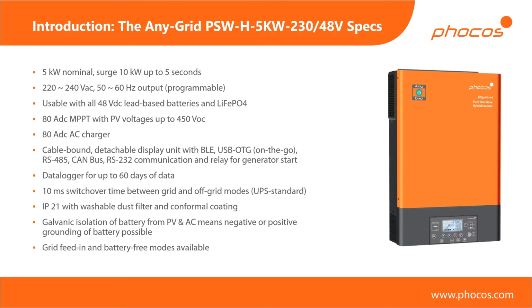Then we have an IP21 rating in terms of the environmental rating. So this is an indoor device. And you can see on the top here, and you'll see a more detailed picture later, it does have washable dust filters on the left and right as well. So you can just wash those out, and there is conformal coating on the PCB assemblies. We have a galvanic isolation between the battery and the inverter unit. So this means you can ground the battery, positive or negative if you like, whichever way you desire. And then finally, we have the grid feed-in mode and the battery-free modes as special modes I'll explain later on.